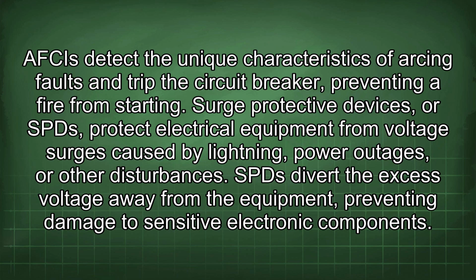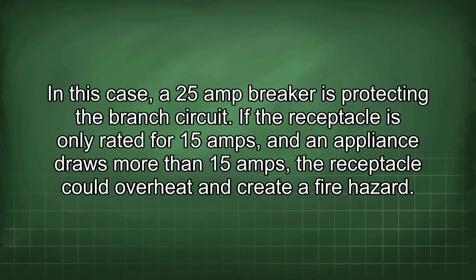Surge protective devices, or SPDs, protect electrical equipment from voltage surges caused by lightning, power outages, or other disturbances. SPDs divert the excess voltage away from the equipment, preventing damage to sensitive electronic components. In this case, a 25 amp breaker is protecting the branch circuit. If the receptacle is only rated for 15 amps, and an appliance draws more than 15 amps, the receptacle could overheat and create a fire hazard.